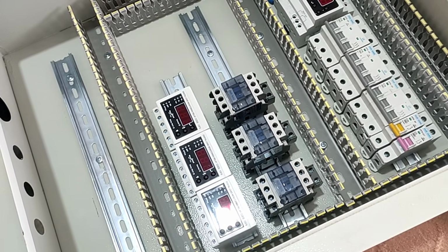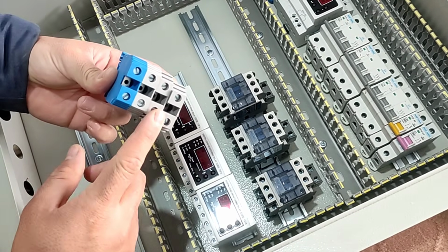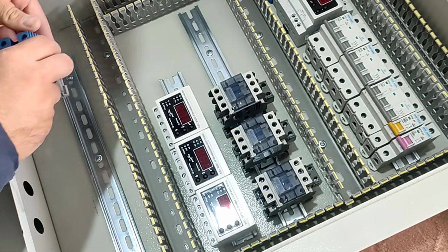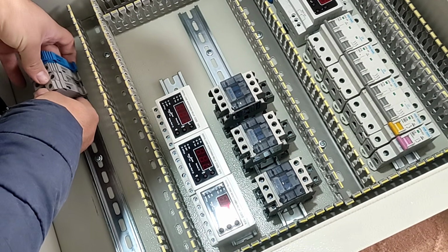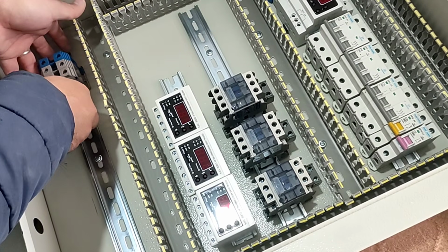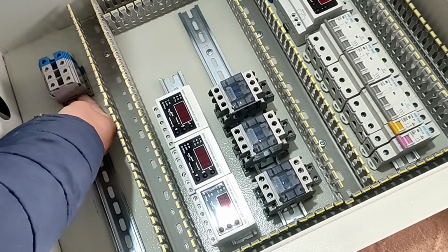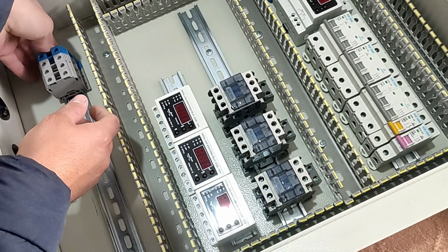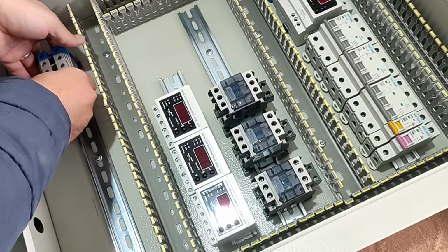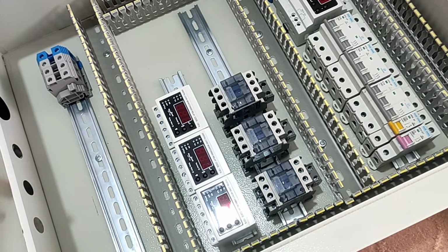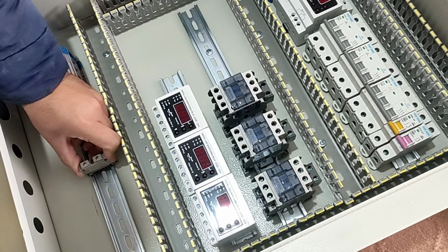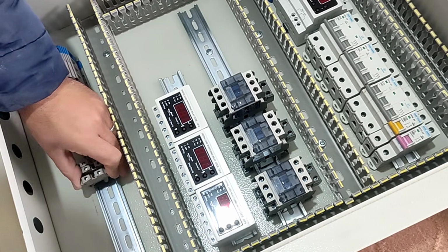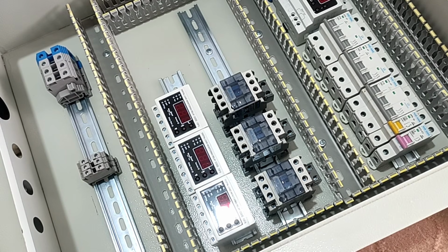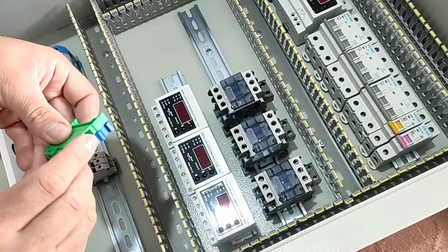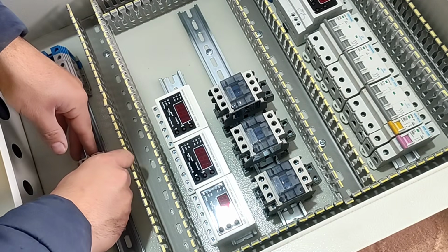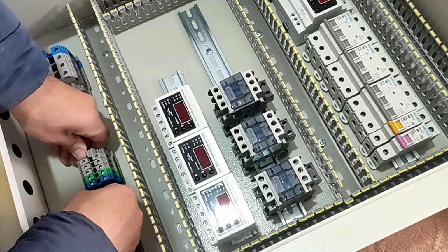In this step, we install the input and output terminals on the rails. At first, we install the three-phase and neutral input terminals. Three-phase and neutral electricity enters the electrical panel using these terminals. We use three terminals for each three-phase output. And we also install two terminals next to each three-phase output when we intend to use a single-phase output.